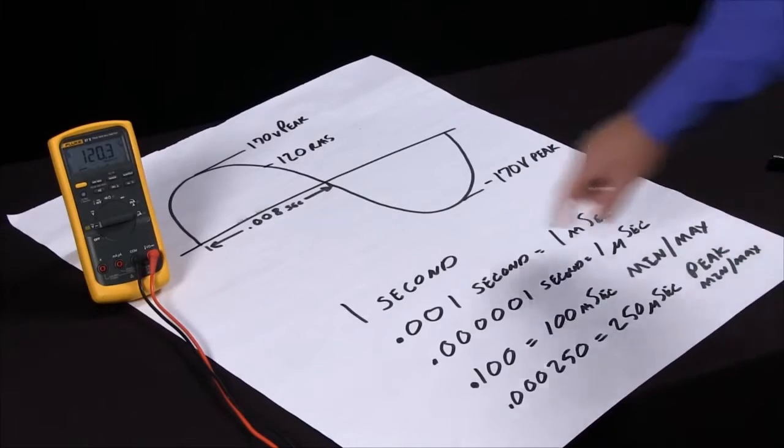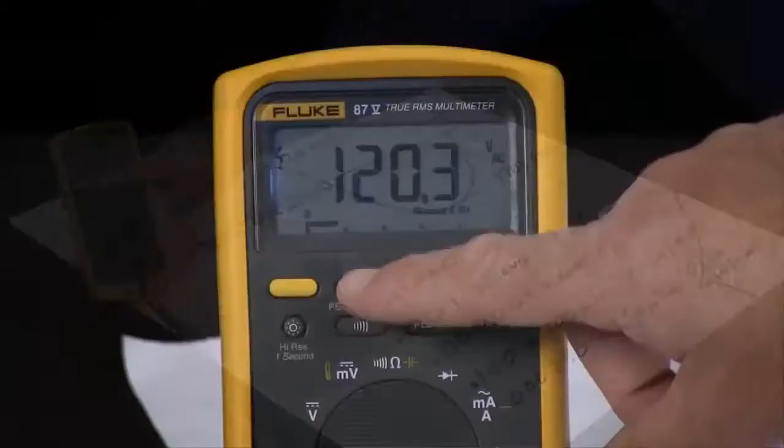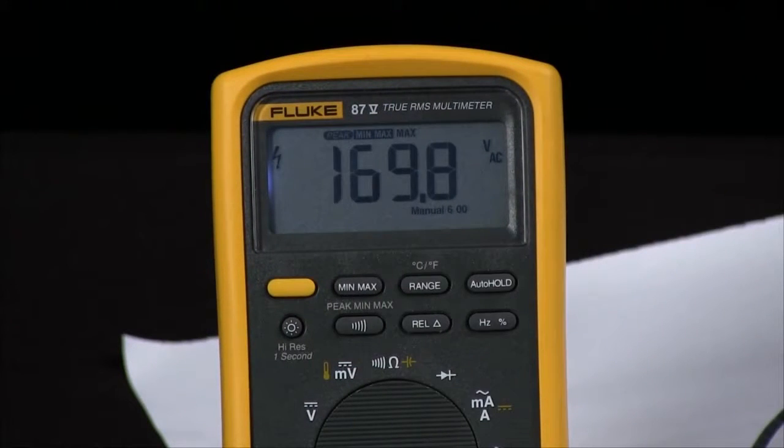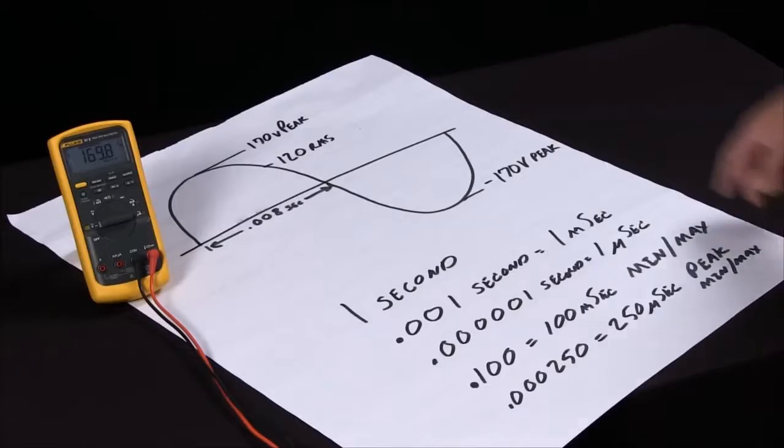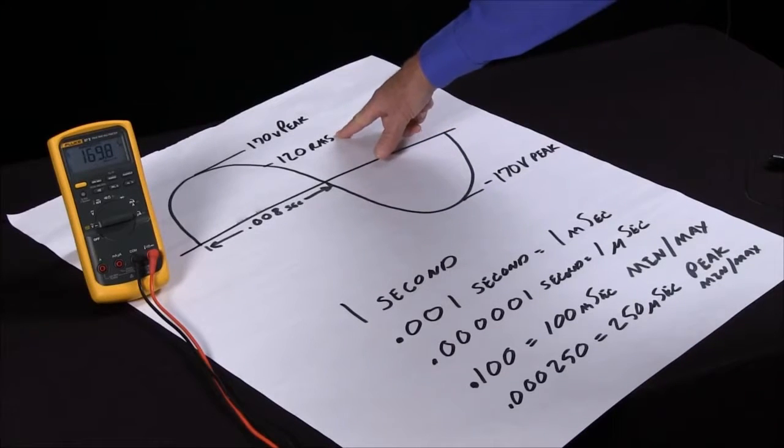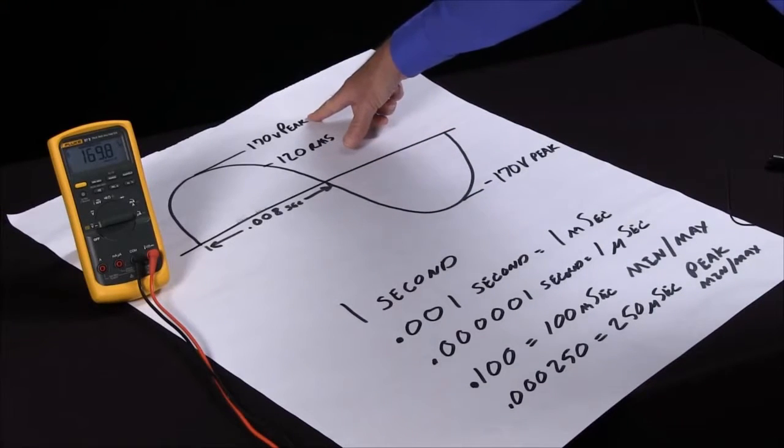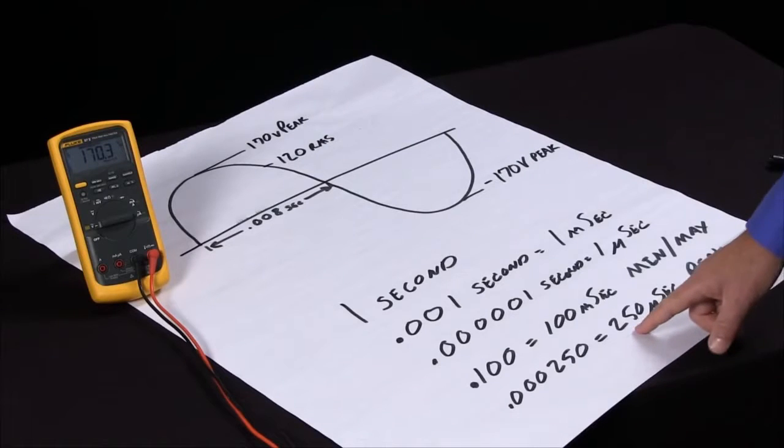When I'm in peak min max to activate that, I hit the min max key and then the peak min max right after that. You can see we've gone from 120 RMS to 170 volts peak because now we have a response time of 250 microseconds.